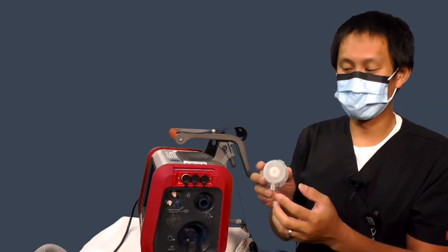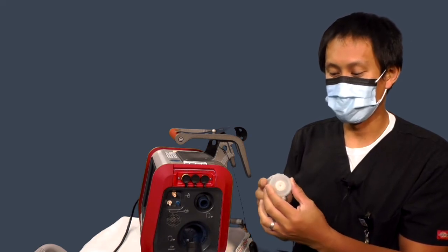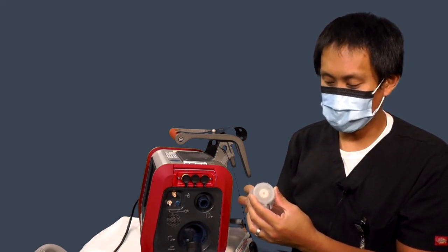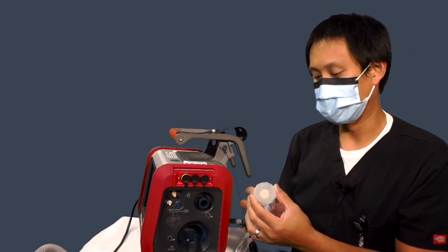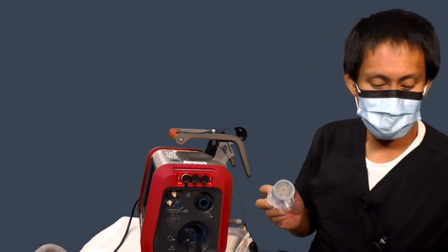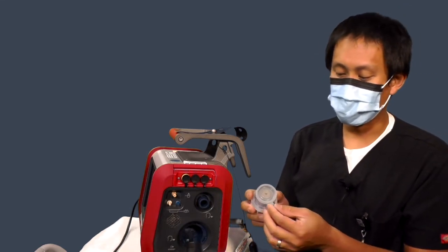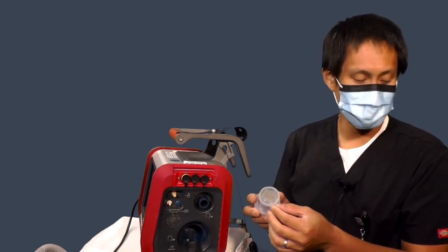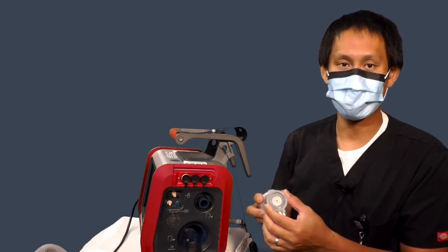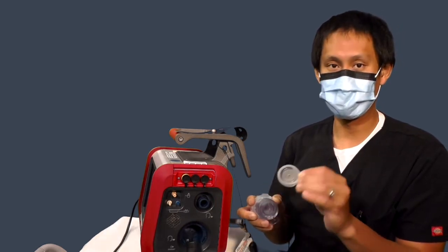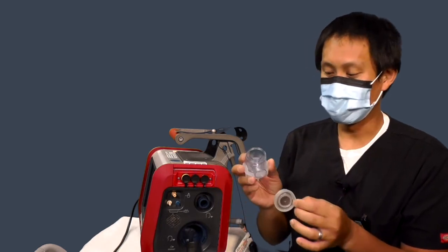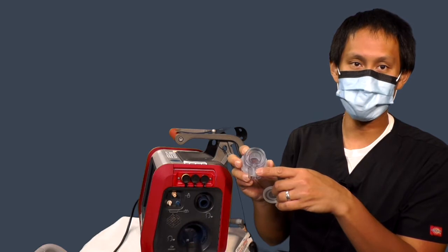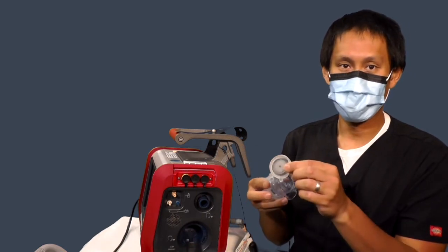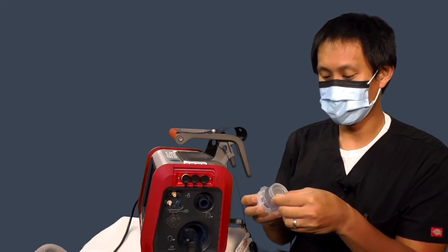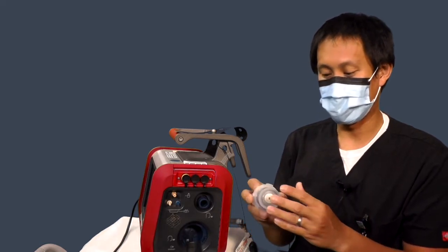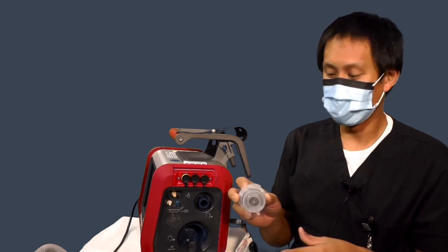What you're going to do is remove the cap. On the side of the expiratory valve, it says remove before use. You want to take that cap off. Be very aware that there is a silicone valve right underneath that cap, and sometimes when you squeeze that cap too hard when you're taking it off, the silicone valve does come off. All you do is line it up with the notch down at the bottom with the corresponding notch on your valve. Put them back together, make sure it's properly seated, and then you're good to go.